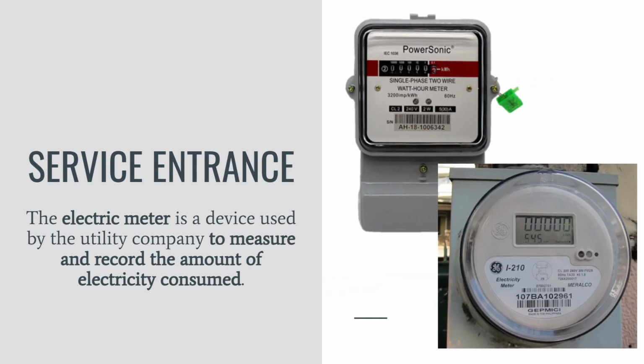The electric meter is a device used by the utility company to measure and record the amount of electricity consumed. It can be a digital or analog electric meter. It is utilized in building services rated up to 400 ampere. This meter is just a little electric motor with a speed proportional to the amount of power consumed.